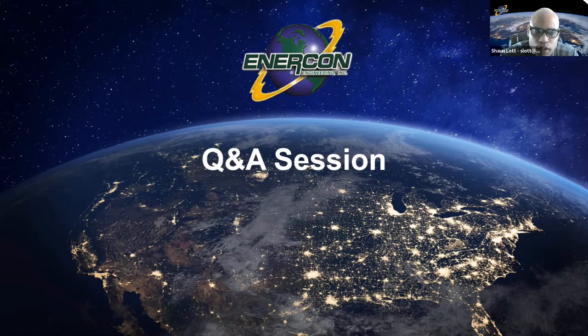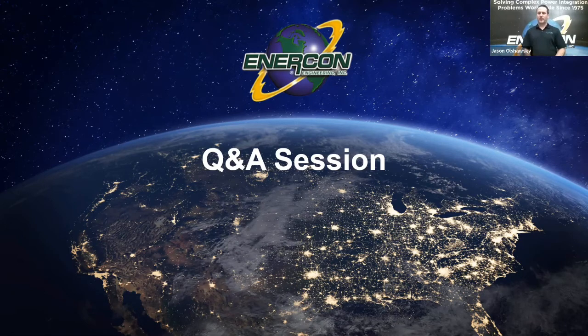Okay, all right, I understand. During the presentation, you also mentioned the LSIG, and if you didn't catch that, it stands for long time, short time, instantaneous, and ground fault. So the question is, low voltage breakers cover LSIG. What about medium voltage breakers? Very good question. In medium voltage, those set points, the trip units, are not local on the breaker. The breaker itself is going to have a shunt trip coil, so what you require in the switchgear is a multifunction relay. A multifunction relay gives you the versatility and ability to program a relay with many different devices and many different set points. It receives voltage and current inputs into the protective relay device, and based on your programming and set points, it sends a signal to that shunt trip coil to open and disconnect that breaker.